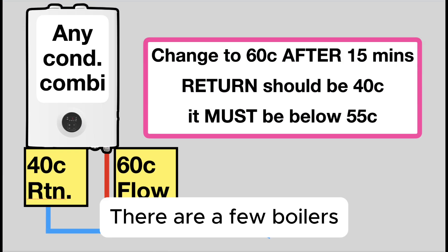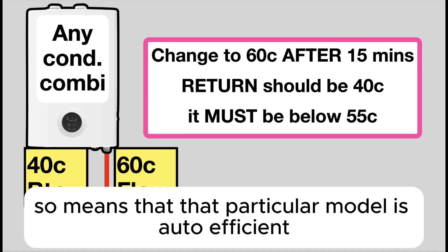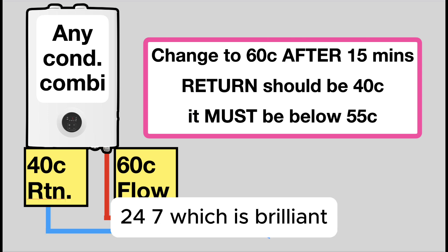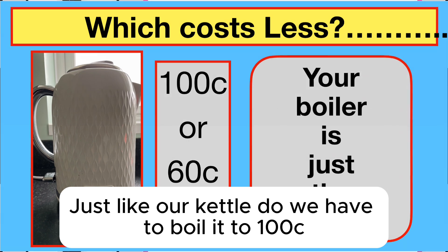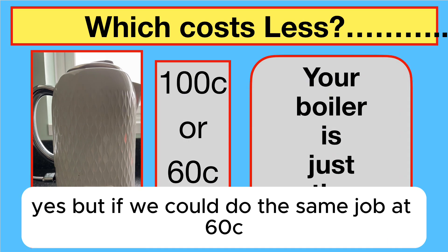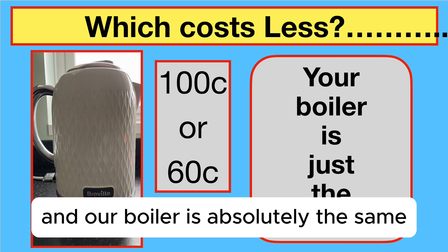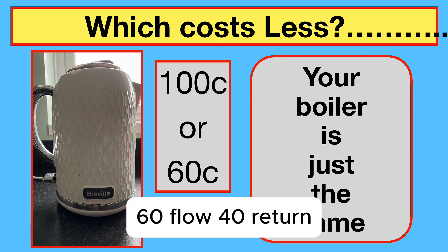There are a few boilers and manufacturers that do this job automatically, so that particular model is auto-efficient 24/7, which is brilliant. Just like our kettle — do we have to boil it to 100 degrees? Yes, but if we could do the same job at 60, that would save us a great deal of money. And our boiler is absolutely the same: 60 flow, 40 return.